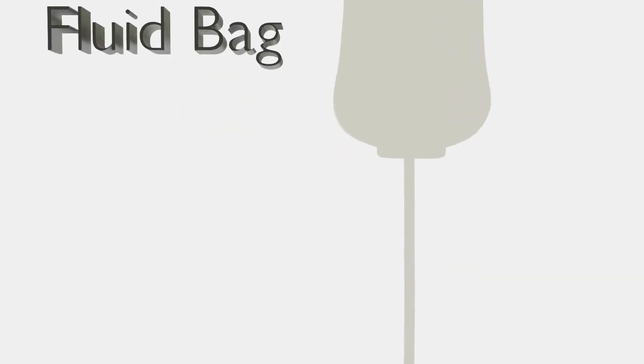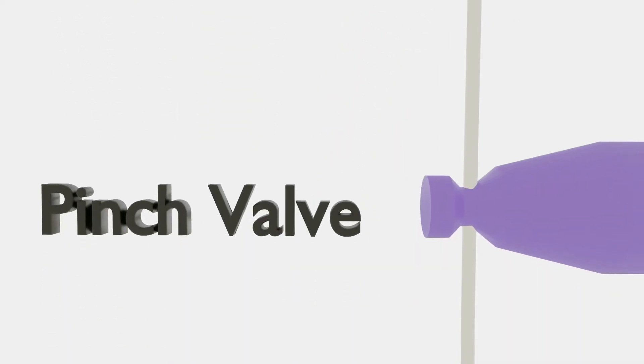Second, the pinch valve. The pinch valve is a solenoid operated device that opens and closes tubes to control the flow of liquids and gases. In pinch valves, there are no dead zones or dead volumes where fluid can become trapped.